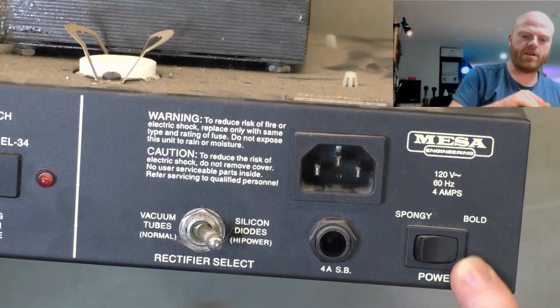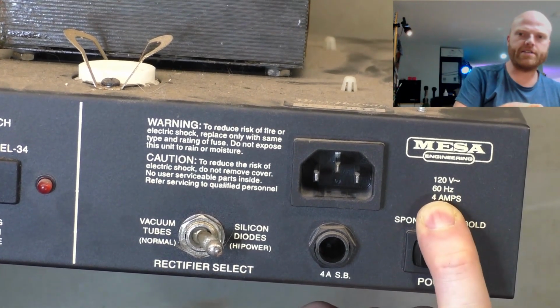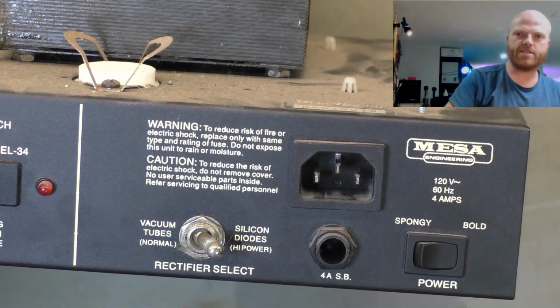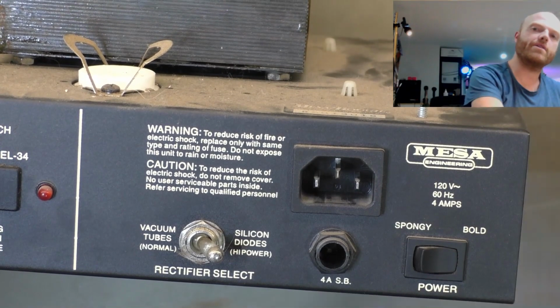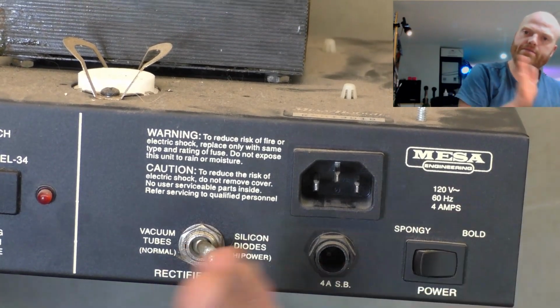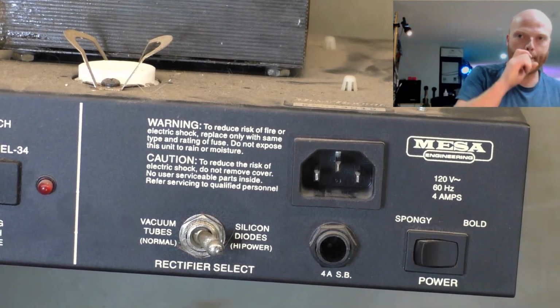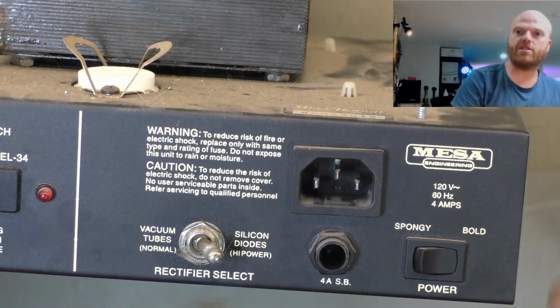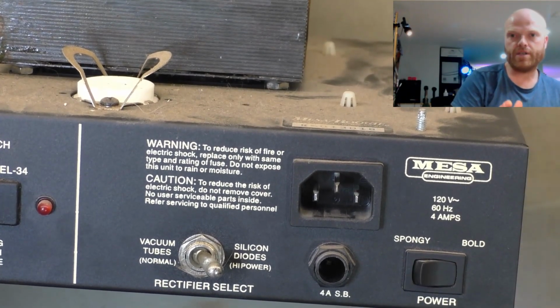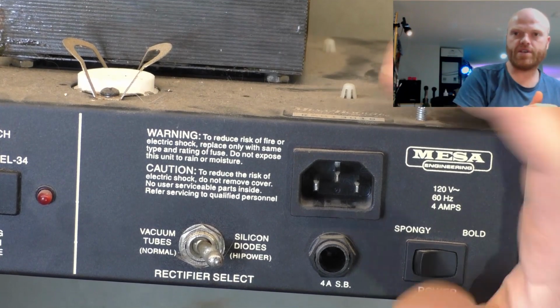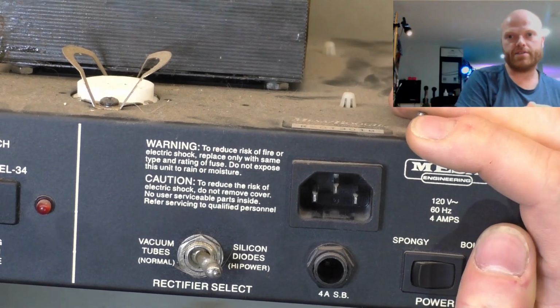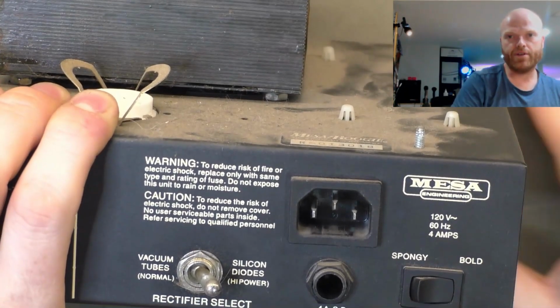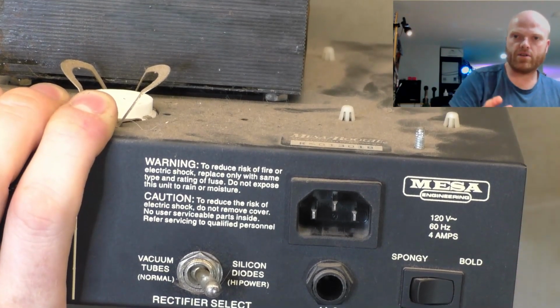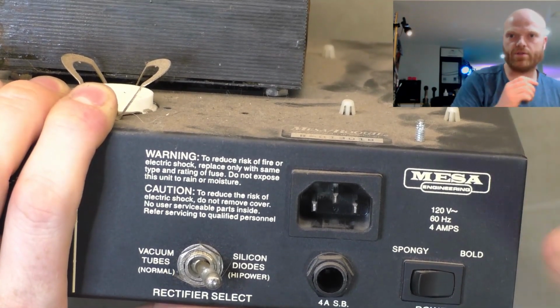So that confirms that there are 120 volts AC, 60 Hertz. If you've got a transformer that's capable of dealing with 60 or 50 Hertz, it'll say 60/50 Hertz. The core size has to be bigger to deal with the lower frequency, otherwise the transformer saturates earlier and doesn't hit its rated power output at 50 Hertz. 60 Hertz, because it's a higher frequency, you can have a smaller transformer core.